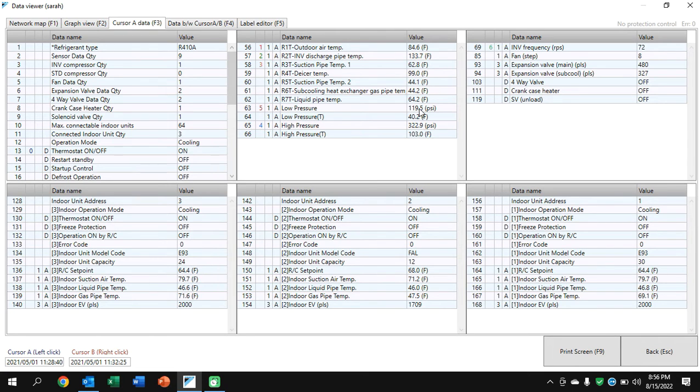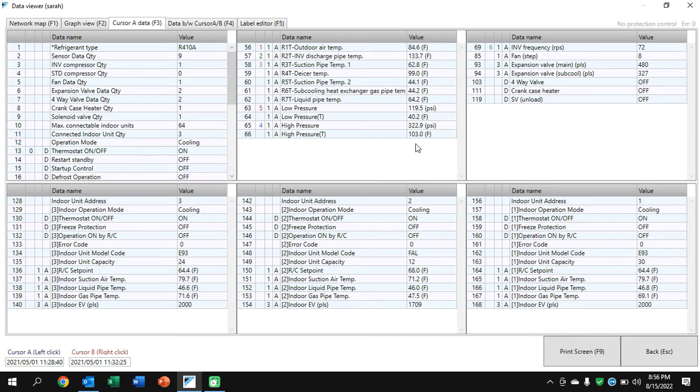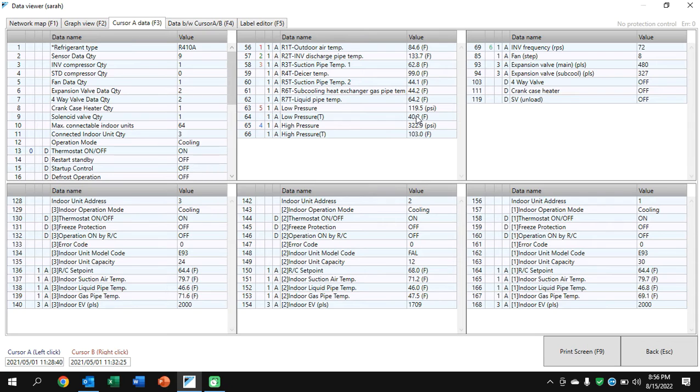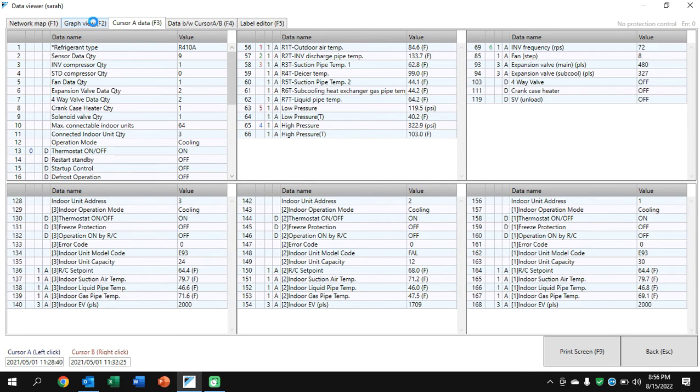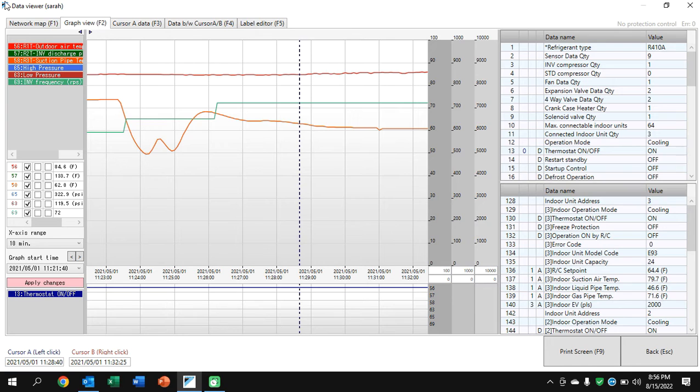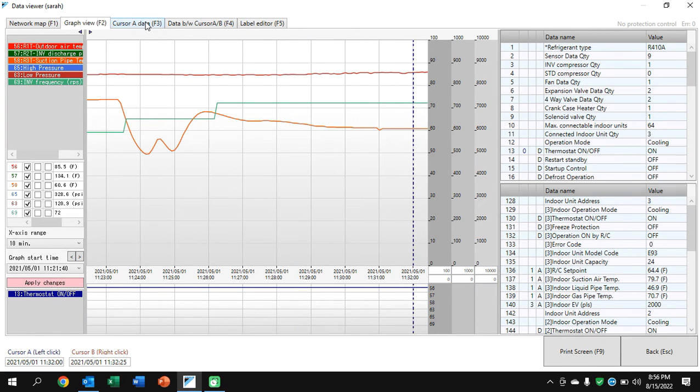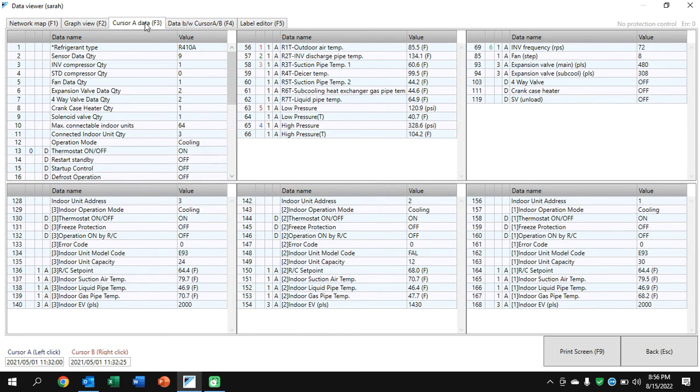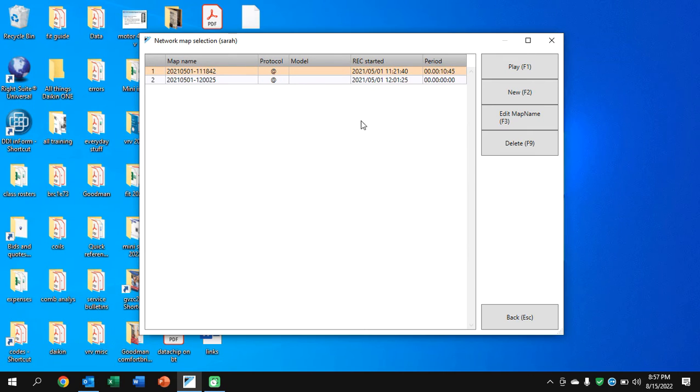If you pay close attention to a couple things. But let's go down and look at the temperature of the coil. Well, VRV, mini split, all the same. 42 to 48 on that indoor coil. You see these are 46 across. The only way we're going to get more cooling out of this is we tell the VRV to be 42. I think this one's programmed a little bit higher up because we're looking at more of a sensible attack and less latent mode. But it's to push more heat into it. So we speed the fan up. And that 46 in a hot room will start rising. And the EV will open. Or the compressor will speed up if the EV is wide open. And in this case, it is open. This is a start up here. We're not very far into the timeline. And after it runs for a while, we'll see the EVs back off. And we'll maintain a temperature.